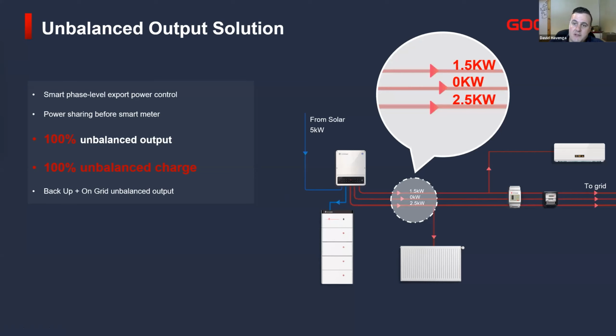You always have to limit to the lowest phase so you don't export out to the grid. Normally that then results in very low PV performance, because all of your loads are split between one and two phases - you can never perfectly balance those phases unless you are running three-phase equipment only.